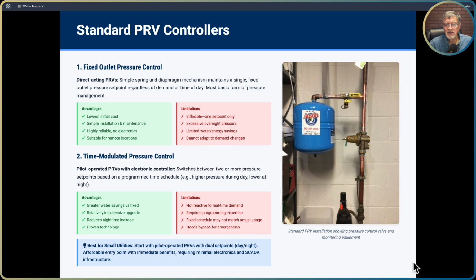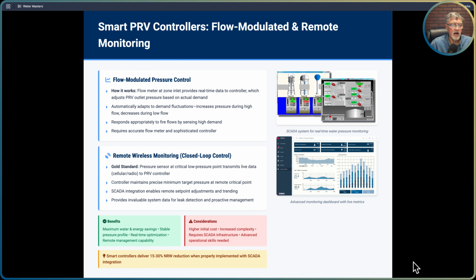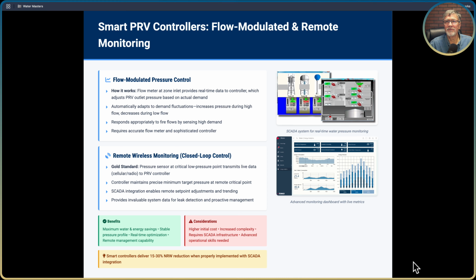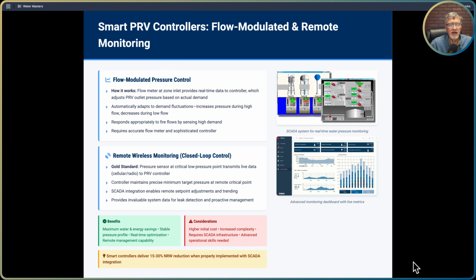So stepping up from there, but beyond that, we now get into the more complicated and more expensive, but really the more sophisticated techniques for managing pressure in your system. So, number one would be flow modulated pressure control. How it works is you're going to have a flow meter at the pressure zone inlet that's going to provide real time data to the controller. So, this is going to be an IoT or Internet of Things type of setup. And then it adjusts the PRV outlet pressure based on the actual demand from that flow meter.